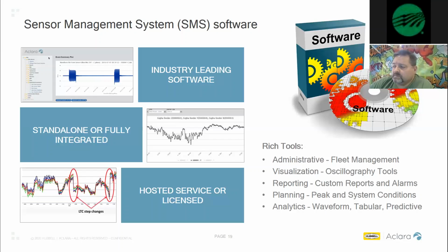From an administrative perspective, the software acts similar to an element manager system. If you have devices out there you're controlling, whether reclosers or cap bank controllers, the SMS acts as an EMS where you can control and manage all the maintenance functions, diagnostic functions, parameter settings, alarm reporting, and firmware upgrades, all over the air. So instead of rolling a truck to manipulate a setting on a sensor, you can do that via your operations center, so the tech doesn't have to go to the field. You're making parameter changes to how sensitive you want the sensor to detect certain anomalies or conditions on the line, and if we release a new firmware package, you can upgrade remotely. All of that, plus all the data coming back from interrogating the sensors, can be done administratively over the air.